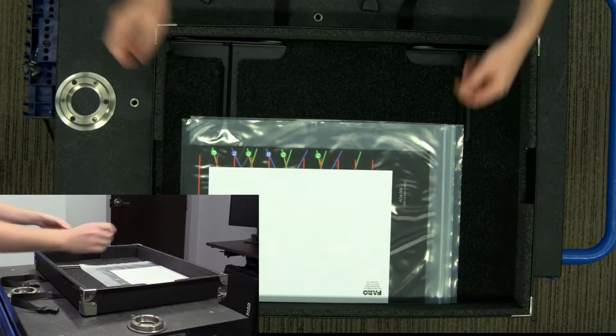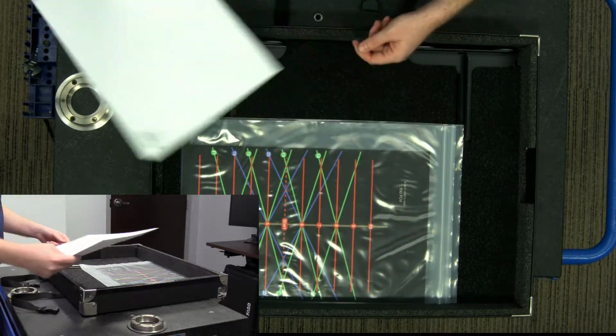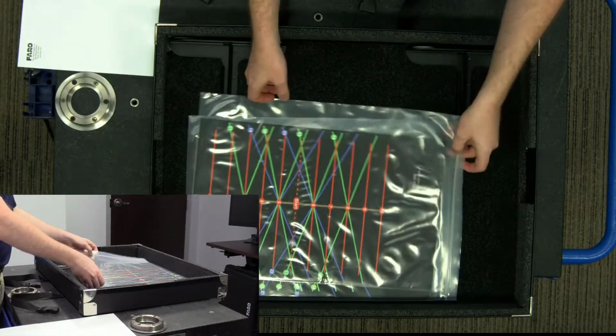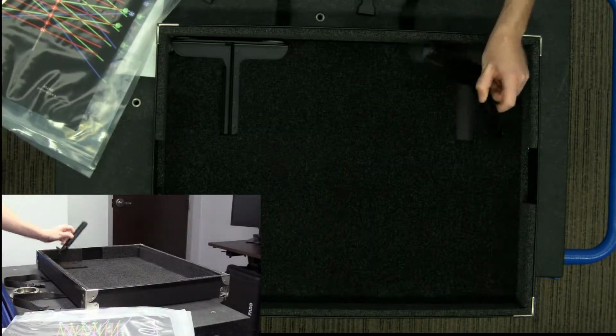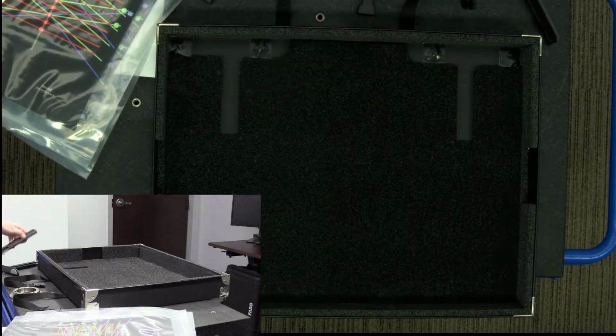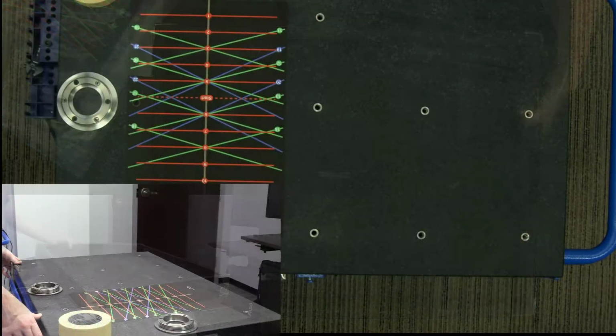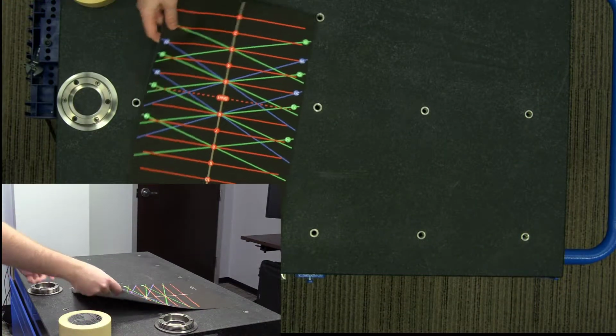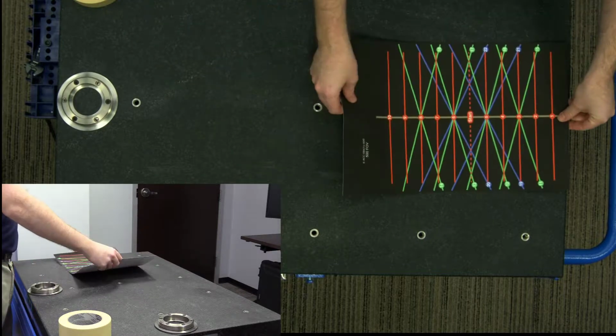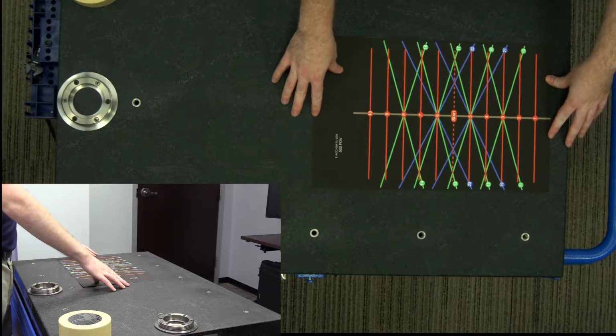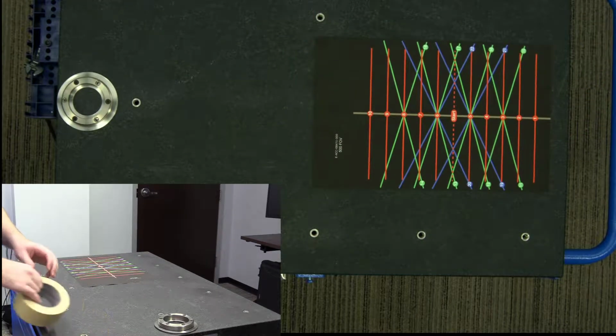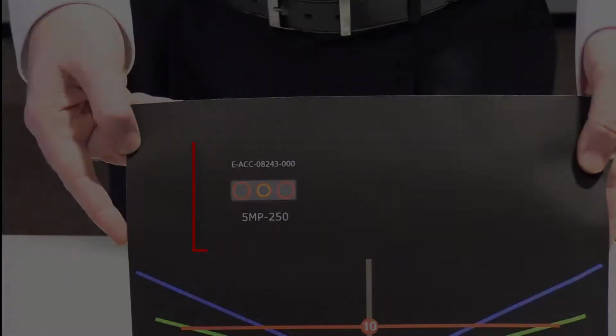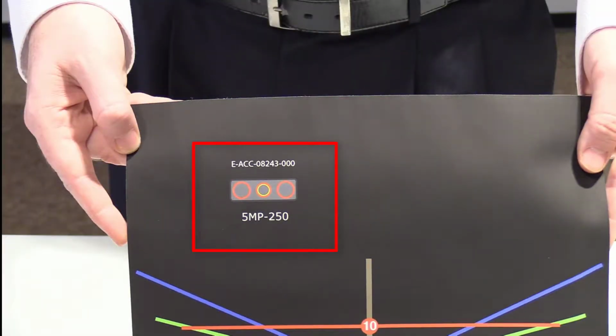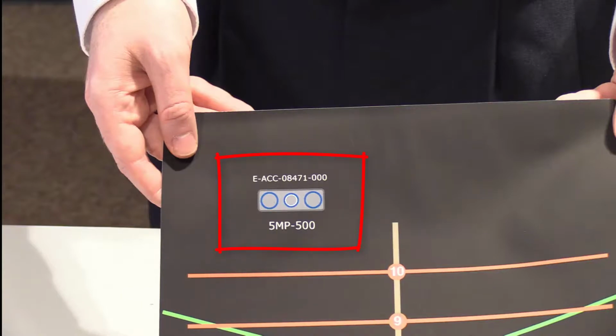Underneath will be the calibration certificate as well as the calibration position templates. Next, remove the calibration plate stands. Choose the calibration position template for the corresponding lens set that you'll be using. Each template has a notation for which lens set it is to be used, for example, 250 mm or 500 mm.